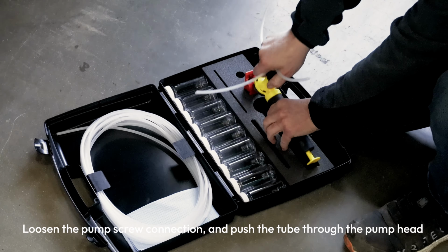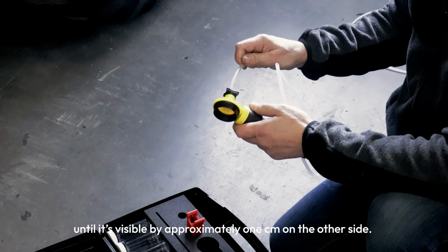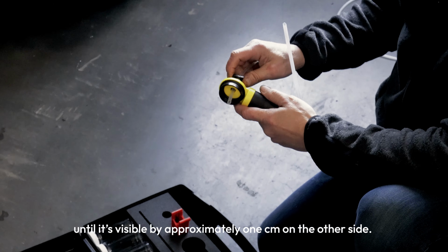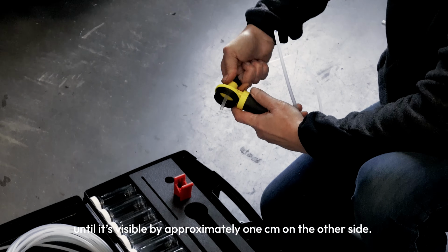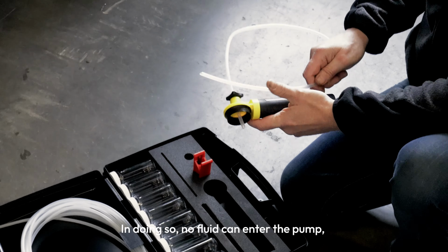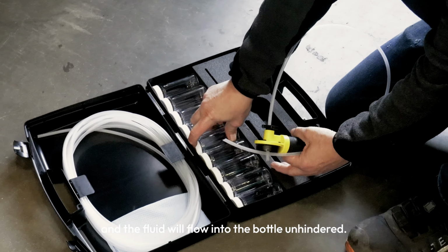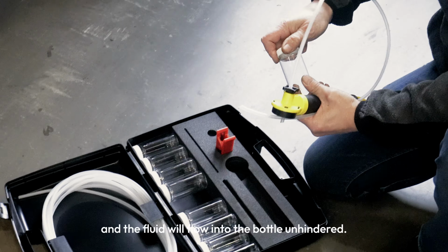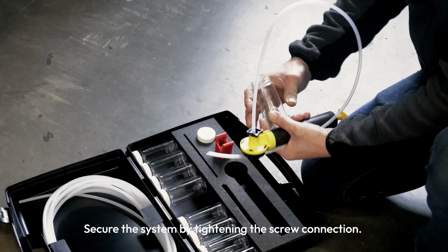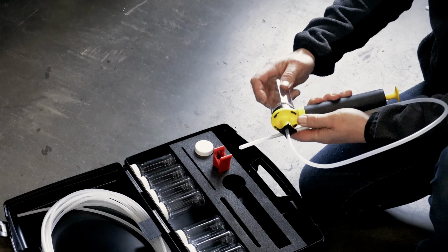Loosen the pump screw connection and push the tube through the pump head until it's visible by approximately 1 centimeter on the other side. In doing so, no fluid can enter the pump, and the fluid will flow into the bottle unhindered. Secure the system by tightening the screw connection.